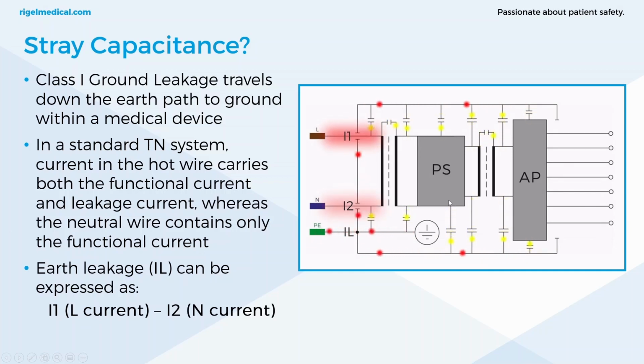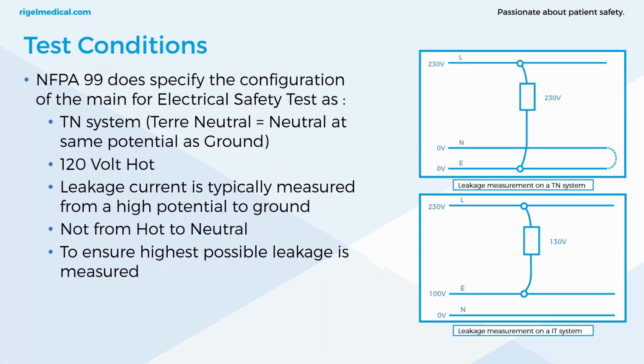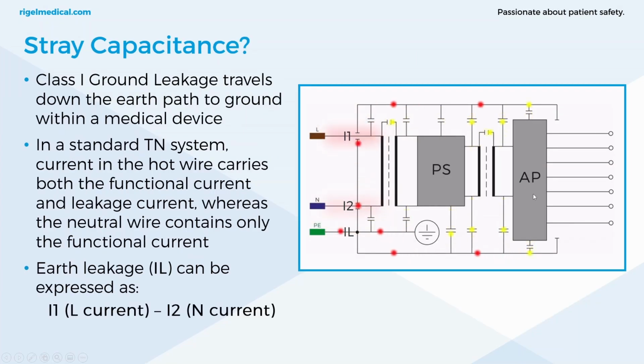So in a different standard, 62353, the live current minus the neutral current is actually one way of determining leakage current. The imbalance between the two conductors is measured, and that gives you the total leakage. So that's one way of measuring that type of current. But NFPA 99 does specify the configuration of mains for electrical safety tests. So leakage is always measured the conventional way, by having a body model in line with the earth conductor or the enclosure or the applied parts, and it's measuring that current directly. So NFPA 99 is always measuring it directly, which is the most accurate form of leakage measurement.